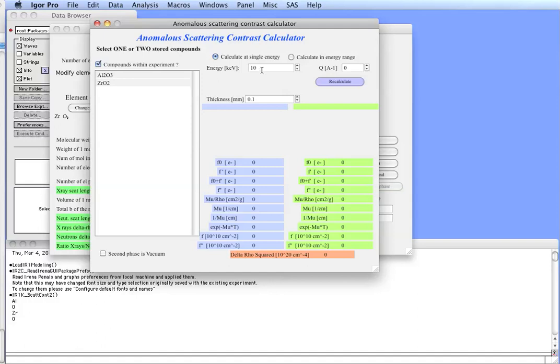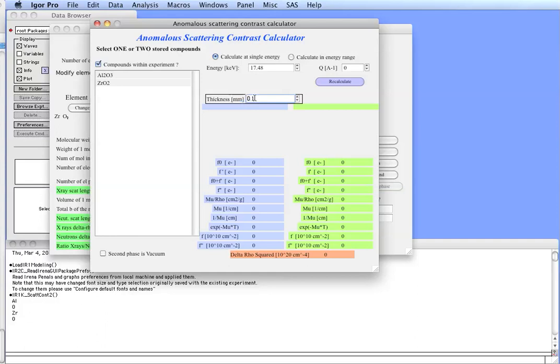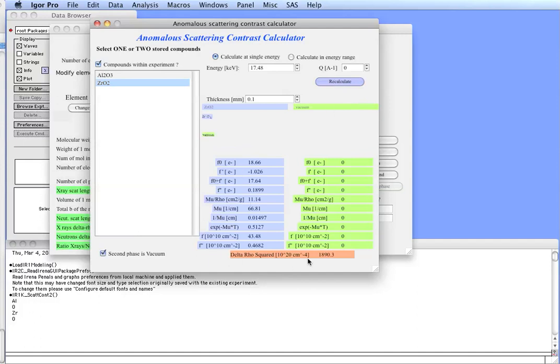In here, we can use Cromer-Lieberman code to calculate the parameters depending on energy. Now, there are two ways you can view this problem. Either you may have a fixed energy instrument and you want to know the parameters for your sample. So, let's say that you have a tube-based desktop instrument with Mo energy, which is 17.48 keV. So, you put energy here. You keep the calculator in calculated single energy, 17.48 keV. If you are doing small angle scattering, you keep Q equal to zero. If you are doing diffraction, you may want to change this number to some higher Q value, whatever you are going to need. Let's assume that your sample thickness is 100 microns, usually 0.1 mm. Let's also assume you have ceramics with voids in it, so the second phase is vacuum. So, keep the second phase here. And then we select zirconium oxide because you want to calculate for zirconium oxide with vacuum. With these parameters selected, we just hit button recalculate. And the table here is populated.